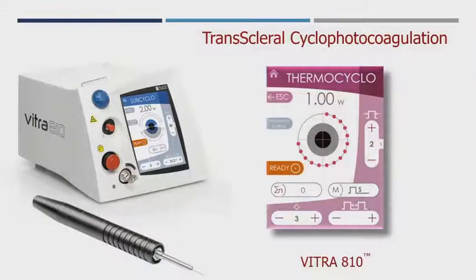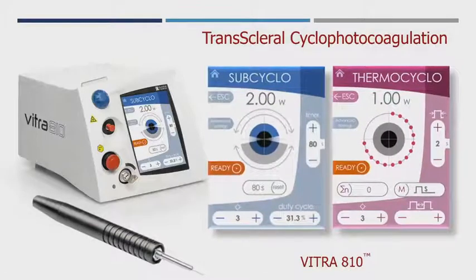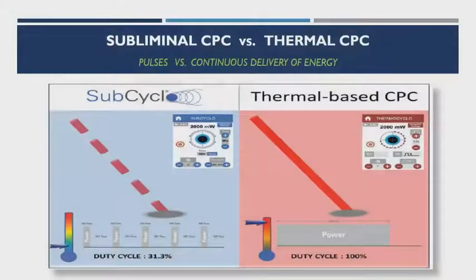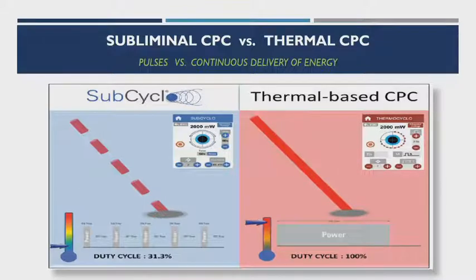Now we have another way to do cyclophotocoagulation: SubCyclo, standing for subliminal transcleral cyclophotocoagulation. We have two technologies in one device. The laser beam is fractionated into very short shots, and between these shots there are gaps during which the tissue has enough time to cool down — the so-called thermal relaxation time — so there is no heating or destruction of tissue. In contrast, traditional thermal CPC delivers energy continuously, 100% going to tissue, which is why it warms up and causes coagulation.